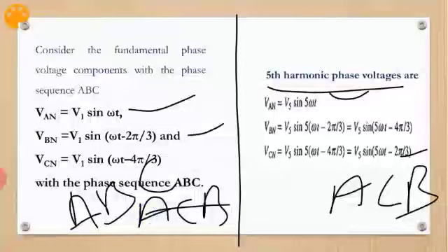As we saw in the equations, the phase sequence of the fundamental and the positive sequence harmonic are the same, hence the rotating field moves in the same direction, whereas a negative sequence harmonic m will move in the direction opposite to the fundamental at m times its speed. Zero sequence components do not produce any rotating field.